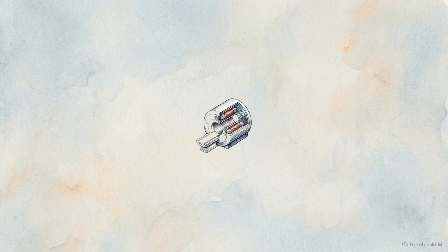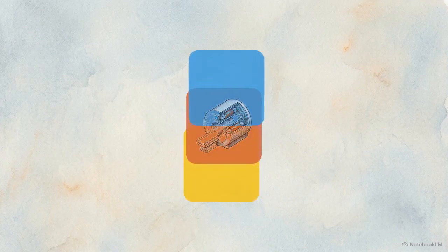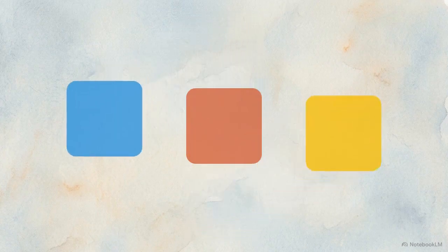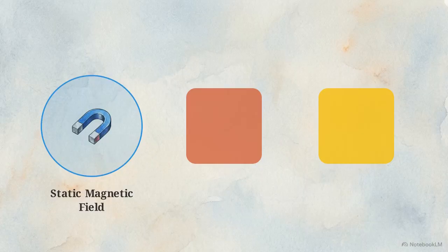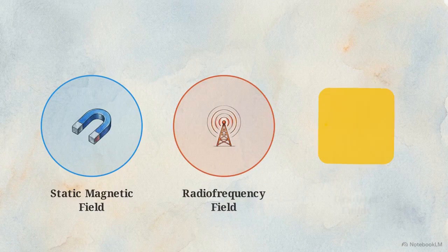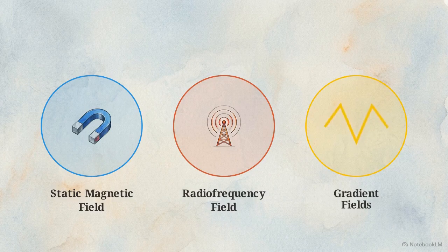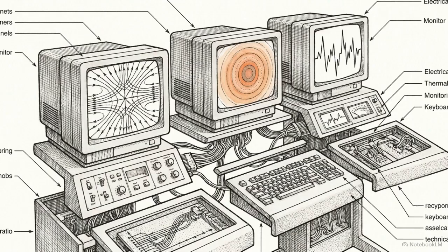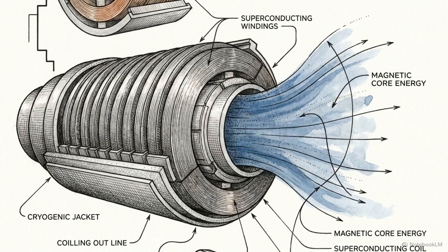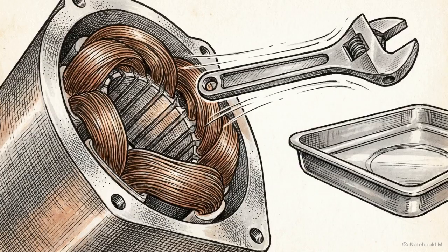Ensuring patient safety requires analyzing the machine's output as 3 distinct physical interactions, rather than a single hazard. These vectors are the static magnetic field, the radio frequency field, and the time-varying gradient fields. Comprehensive safety requires the simultaneous management of these 3 environments, as each interacts differently with human physiology and implanted materials. The foundation of the system is the static magnetic field. Powered by superconducting coils, this field is always active and generates immense kinetic force.